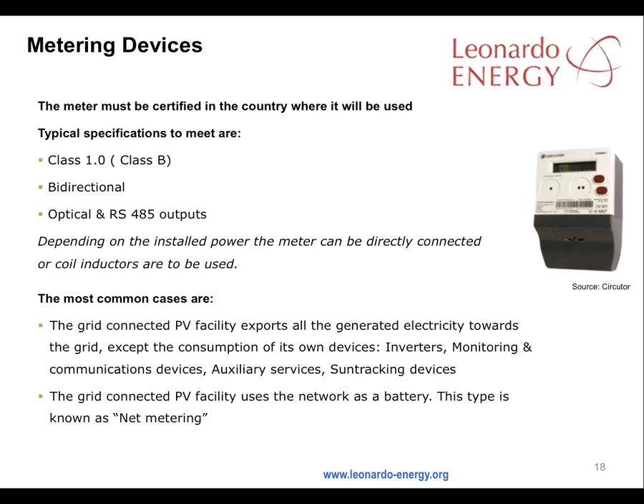Meters must meet the certification requirements of the countries where they are used. Typical specifications to meet are that they are class 1 — that's class B standard — and that they are bi-directional with optical and RS-485 outputs. Depending on the installed power, the meter can be directly connected or coil inductors can be used. The most common scenarios are a grid-connected PV facility that exports all of its generated electricity to the grid, except for that consumed by its inverters, monitoring and communications devices, auxiliary services, and sun tracking devices.